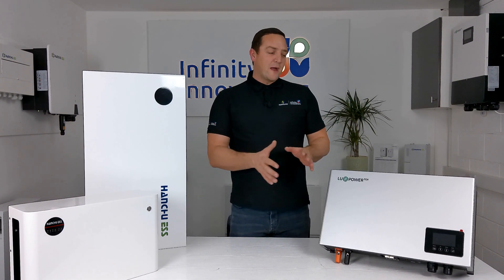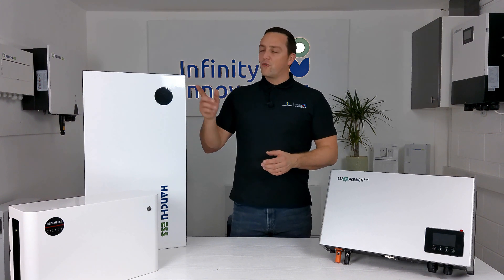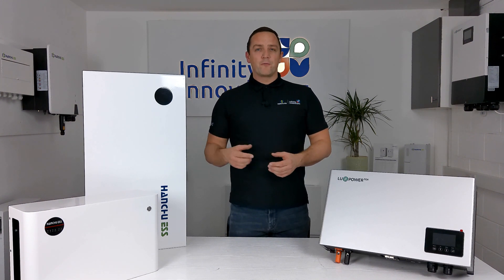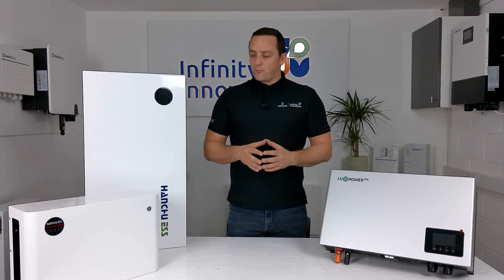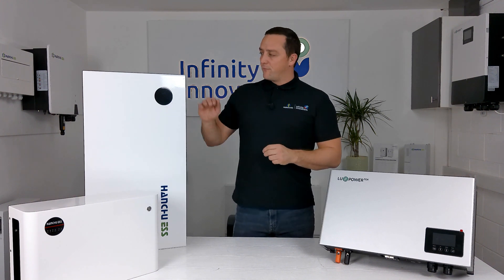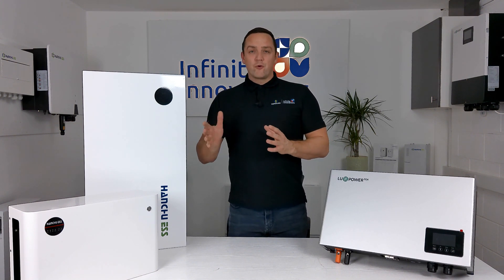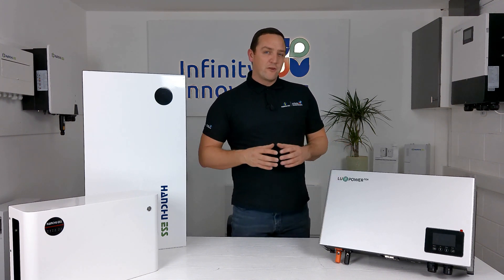The maximum number of batteries you can add to a LuxPower AC controller is eight. We use the Hanchu range for the 9.4 kWh and 3.2 kWh batteries, and also the U-Home range which is a 2.4 kWh modular battery. You can use 1 to 8 of either, but to get the maximum charge and discharge rate out of this unit you need a minimum of two 3.2s, just one 9.4, or three U-Homes. So while it supports 1 to 8 batteries, bear in mind you do need a minimum number to reach the maximum charge and discharge rate.